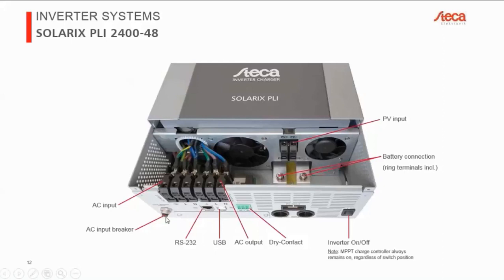We have an AC input breaker, because of course we can switch over to the AC source. And in that case, we still need to have some kind of protection if you're overloading the input source. So in this case, we have a 30 amp input breaker. So that's the maximum current that you can provide basically from the AC source to the load. It's 30 amps.